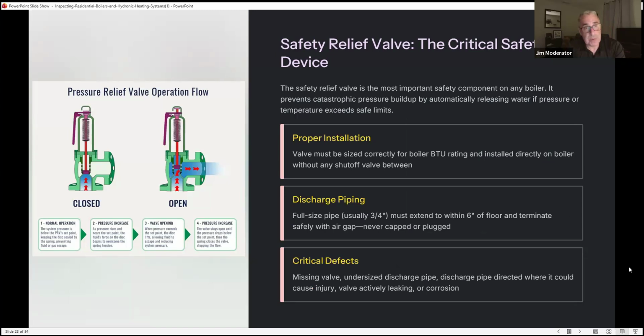Safety relief valve, the critical safety device. The safety relief valve is the most important safety component on any boiler. It prevents catastrophic pressure buildup by automatically releasing water if pressure or temperature exceeds safety limits.